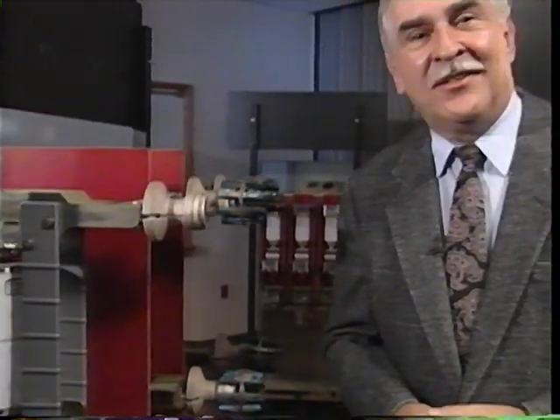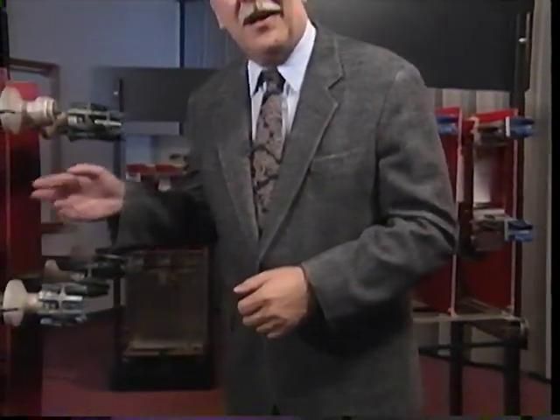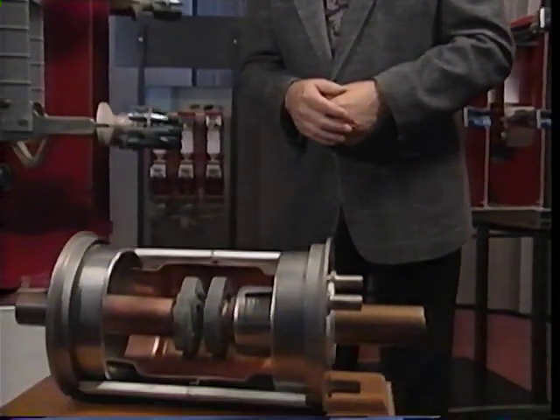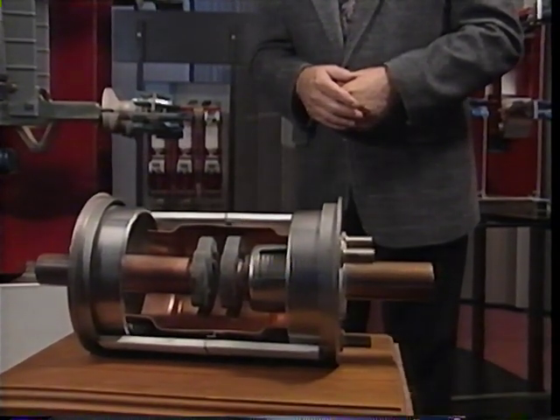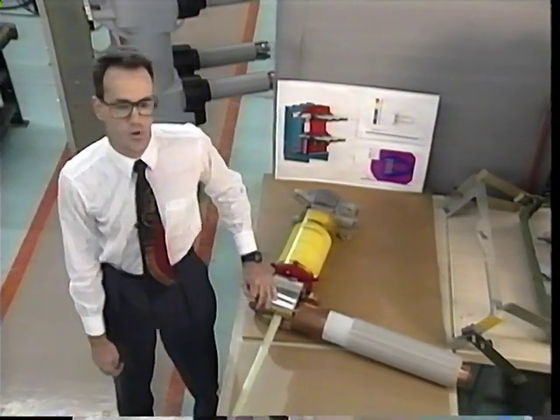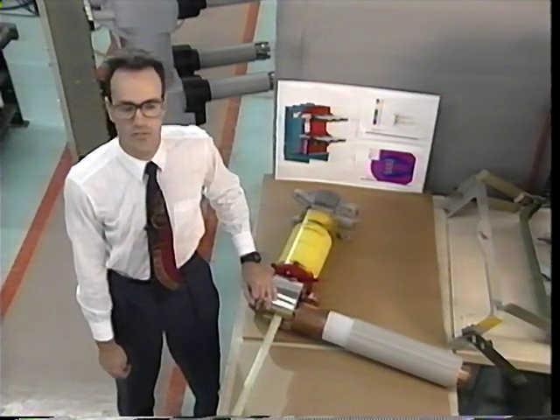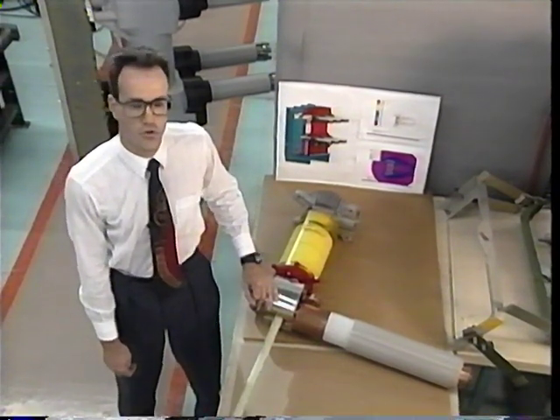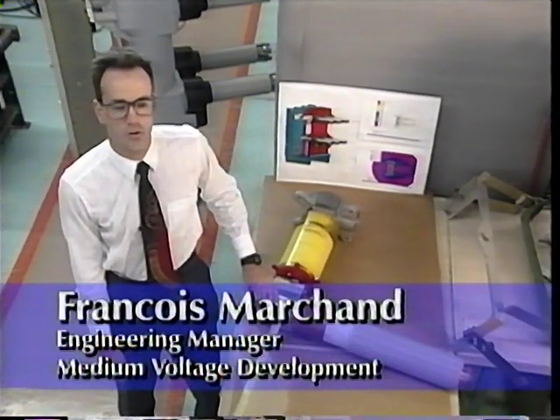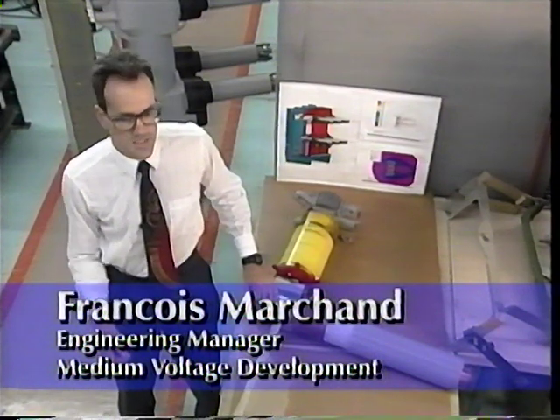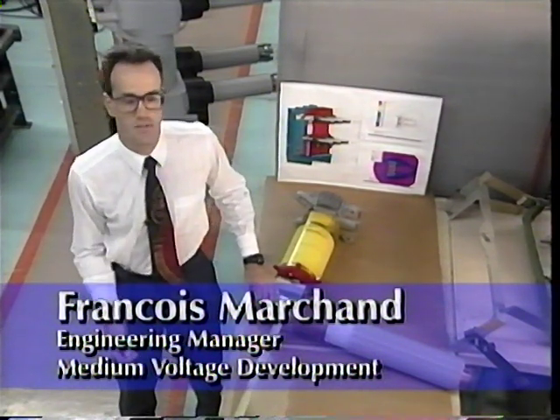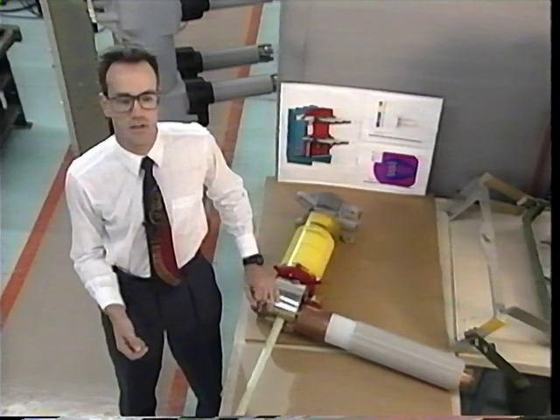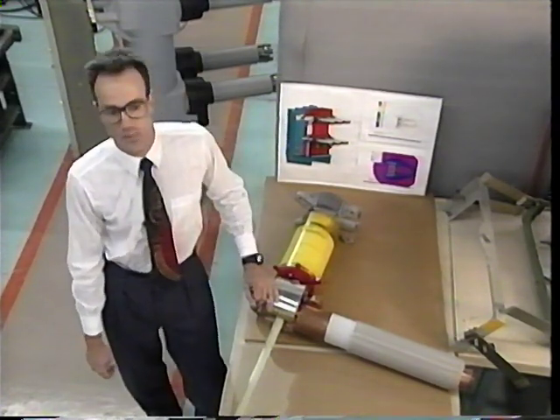That same basic science of arc interruption is also applied to our vacuum interrupters, a product widely acknowledged as the world's best. Our challenge in the vacuum interrupter is to make the arc behave until it's natural for it to go out. To accomplish that, we use many different contact shapes: spiral, petals, cups, axial magnetic field type contacts, which seem to control the arc best.